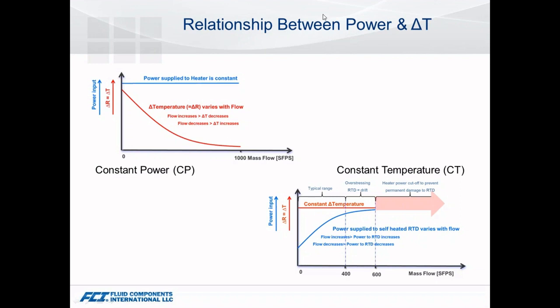This next slide shows the relationship between those designs. With constant power, we're putting a fixed current into the heater, and as flow increases, you see the delta T change — that delta T is able to go out a bit further in our measurements, up to a thousand standard feet per second. On the constant temperature side, we're maintaining that temperature differential and putting current into it in relationship to the flow, but there are some potential limits on your high-end flow rate capability. You also typically want to limit the amount of current going into that sensor to avoid pre-aging sensors, which would lead to potential drift and failure.